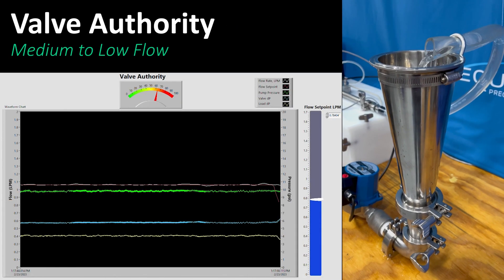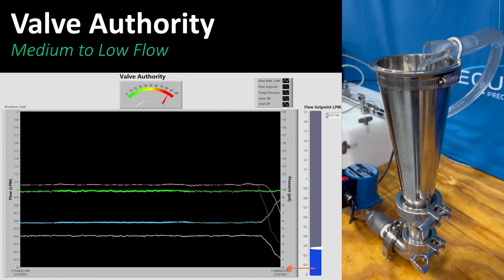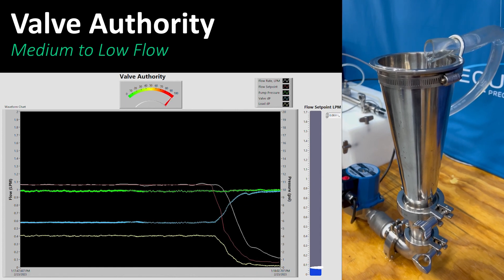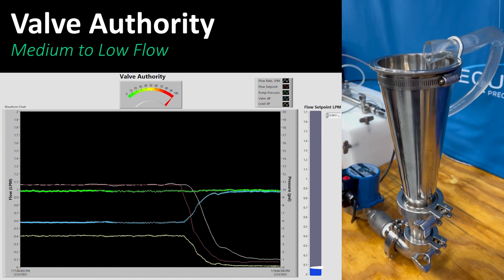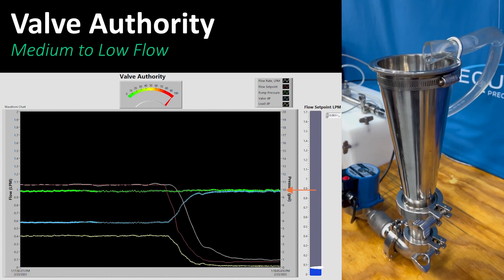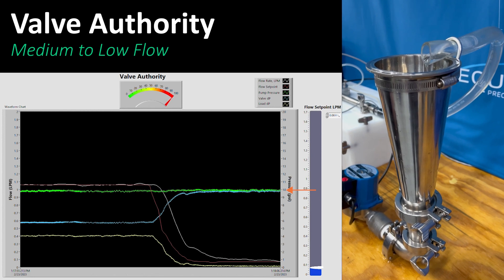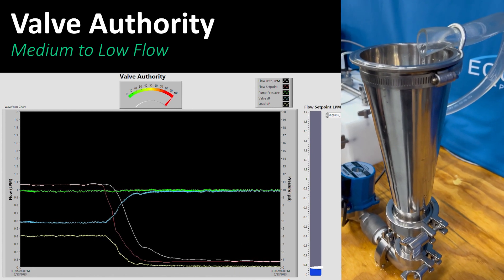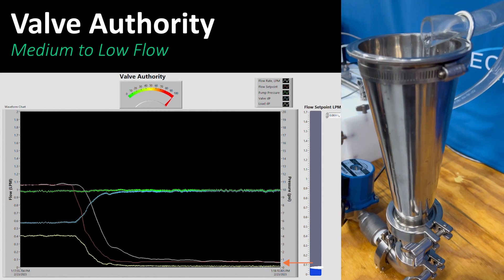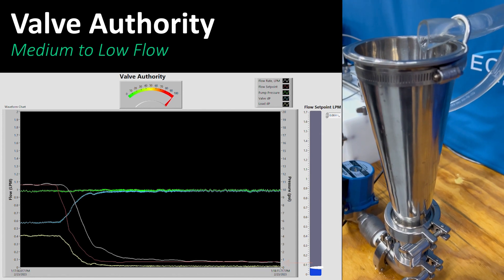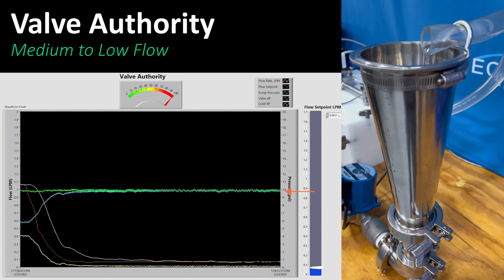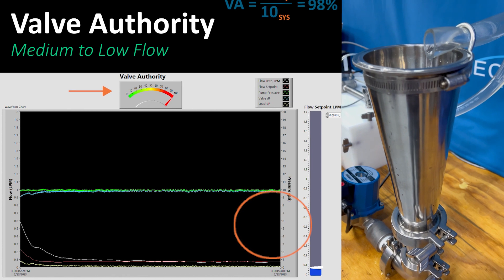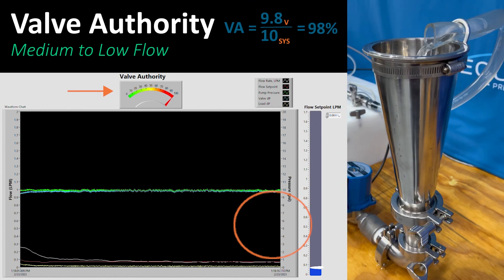The flow rate is 0.07 liters per minute, or 1% of max flow. The pump is producing 10 psi. The coil resistance has dropped to 0.2 psi. The differential across the control valve has risen to 9.8 psi. The valve authority is therefore 9.8 divided by 10, or 98%.